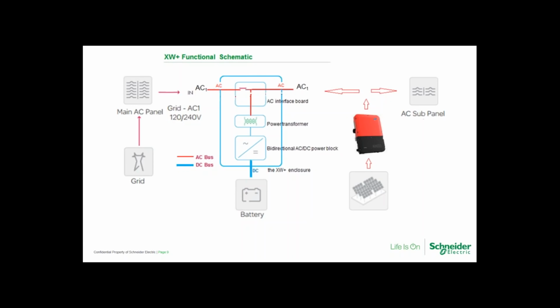This also brings up another point for customers that are in Hawaii or California, and that is the new rules for smart grid interactivity, such as UL 1741 Supplement A, Rule 21, and HECO. These are smart grid functions, and the question is, will AC coupled systems be allowed permission to operate if we're merely inserting a battery-based system between the grid and a compliant inverter? My take on that is, why not? I mean, if the XW or the Connect SW is merely acting as a gateway to pass the grid power through and has no bearing on interacting with the grid whatsoever, it's just there to provide backup so you can AC couple. I don't know why that would be denied, but it's certainly a question that remains to be answered, and it's going to be one that I'm going to be following closely.